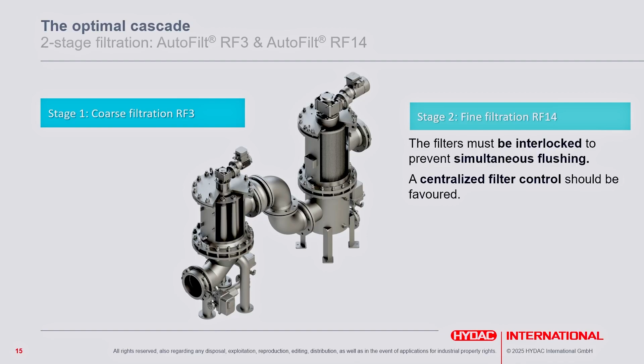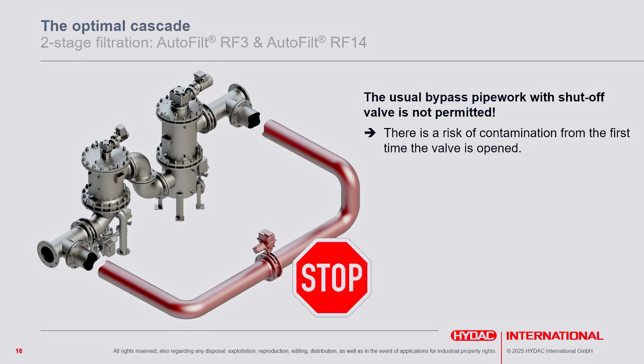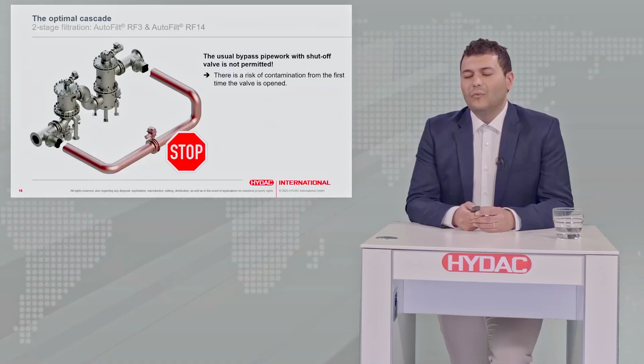Now, together and in discussion with our customer, we need to put up the system. What is not allowed is to use a simple bypass valve, as we often see with filters in general. The reason is these larvae: when they enter the system, upstream of our filter, there are still larvae. When they go into this piping system over the backflushing line, they have the time to grow, the time to settle, the time to build up colonies. And when our filters go into revision, we open, or the customer opens, this backflushing line, and there is a really huge risk of contamination from the first time the valve is opened. This is why we need some kind of a redundant system.